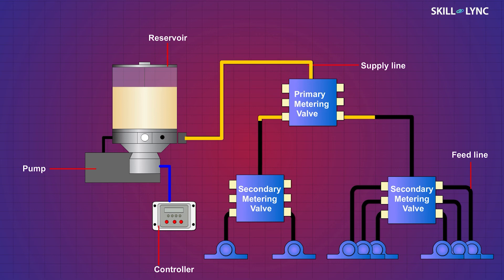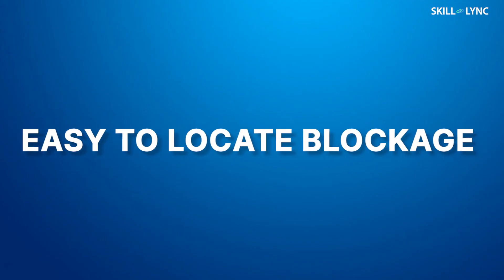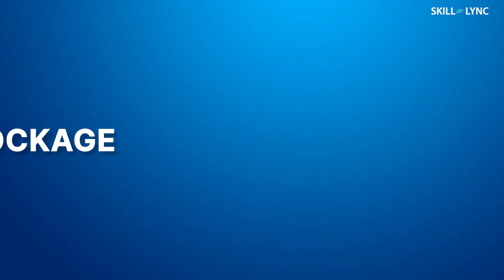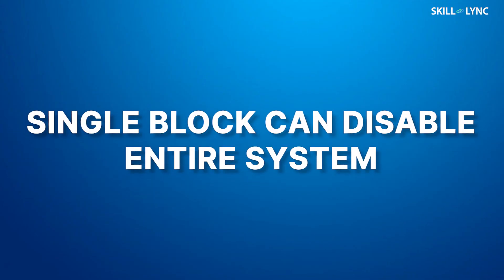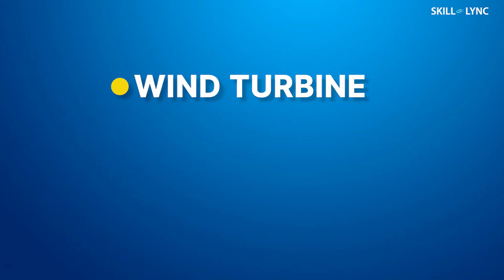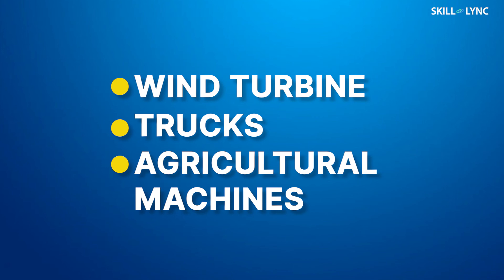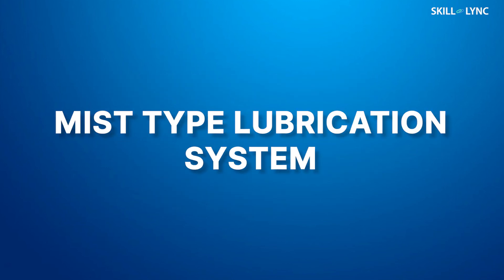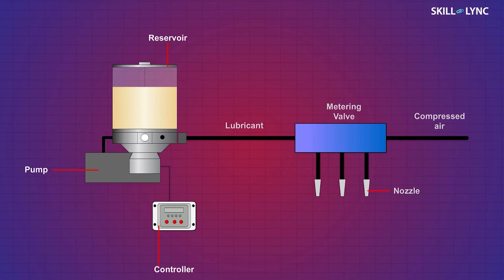The third type is the single line progressive system. In this type, the lubricant from the pump reaches the primary metering valve, from where it is distributed to the secondary metering valve, and it goes further. Because of this structure, it is easy to locate a blockage, but a single block can disable the whole system. This system is used in wind turbines, trucks, and agricultural machines.